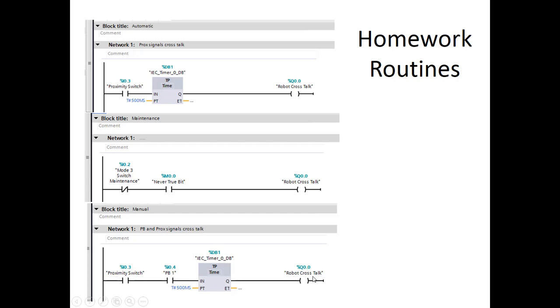Okay, so here we go again. We've used this output 1, 2, 3 times. Is that a good idea? Well, it works, but maybe that's not the best idea. Maybe it would have been better if this would have been M1. I'm sorry, we've already used the first M0.0. This could be M0.1, M0.2, and M0.3.